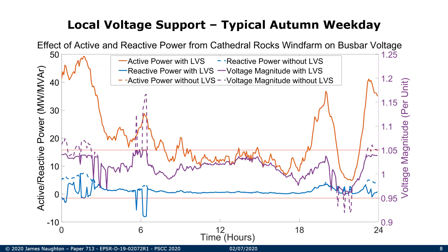So if we show where the voltage limits are, it can be seen that when the virtual power plant is providing local voltage support, the nodal voltage remains within allowable limits. And without it, this node's voltage magnitude would violate both the minimum and maximum voltage constraints. And it can be seen that whenever the voltages in the two cases diverge, there is also a divergence in the reactive power output of the device. So this is an example for a single device on a single node, but the VPP framework controls all the devices in such a way that this voltage support is achieved across all nodes in the network.